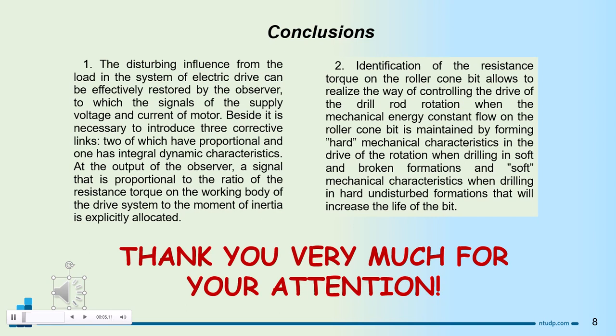Conclusions. The disturbing influence from the load in the system of electric drive can be effectively restored by the observer, to which the signals of the supply voltage and current of motor. Besides, it is necessary to introduce three corrective links, two of which have proportional and one has integral dynamic characteristics. At the output of the observer, a signal that is proportional to the ratio of the resistance torque on the working body of the drive system to the moment of inertia is explicitly allocated. Identification of the resistance torque on the roller cone bit allows to realize the way of controlling the drive of the drill rod rotation when the mechanical energy constant flow on the roller cone bit is maintained by forming hard mechanical characteristics in the drive of the rotation when drilling in soft and broken formations, and soft mechanical characteristics when drilling in hard, undisturbed formations that will increase the life of the bit.